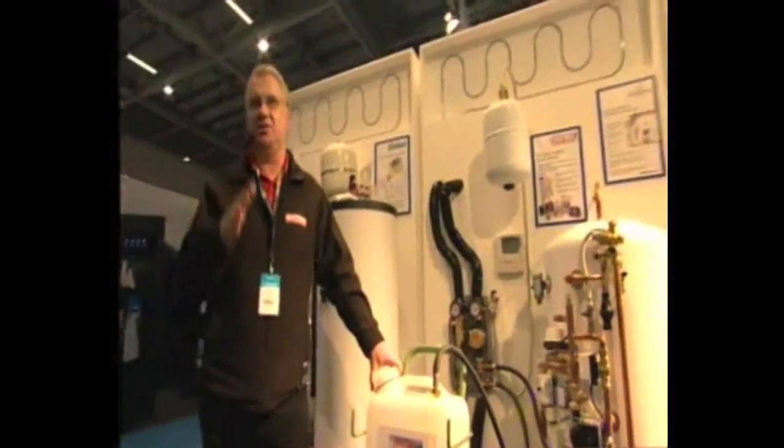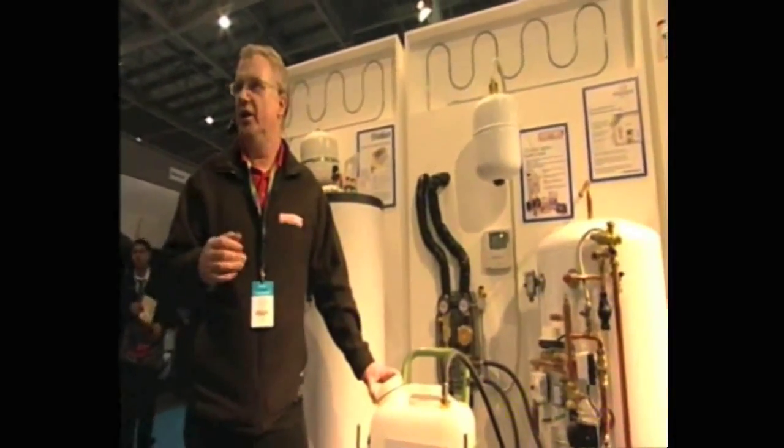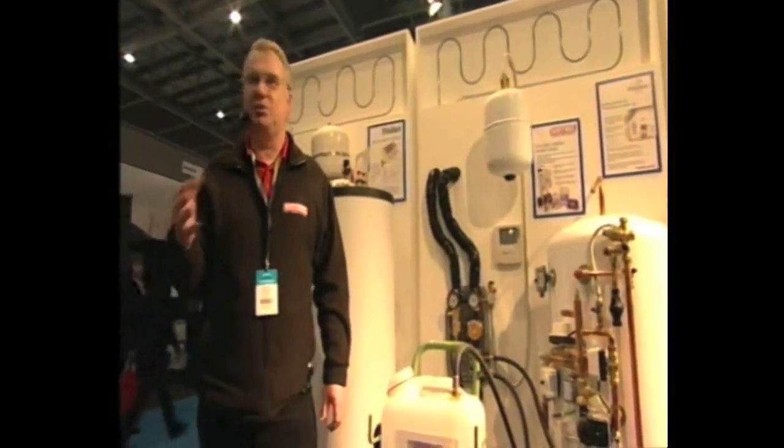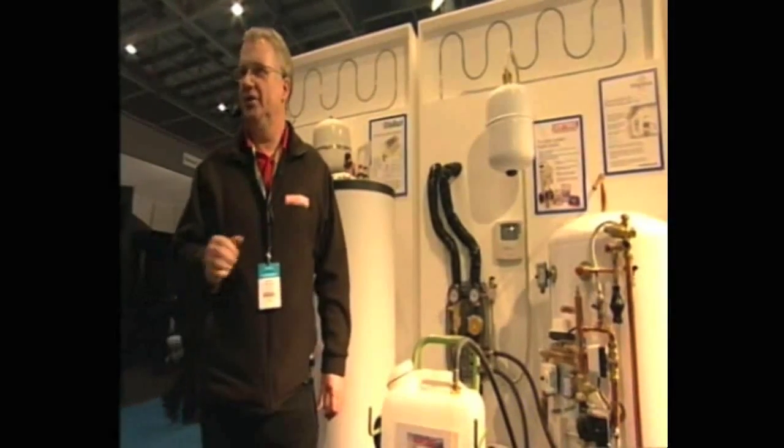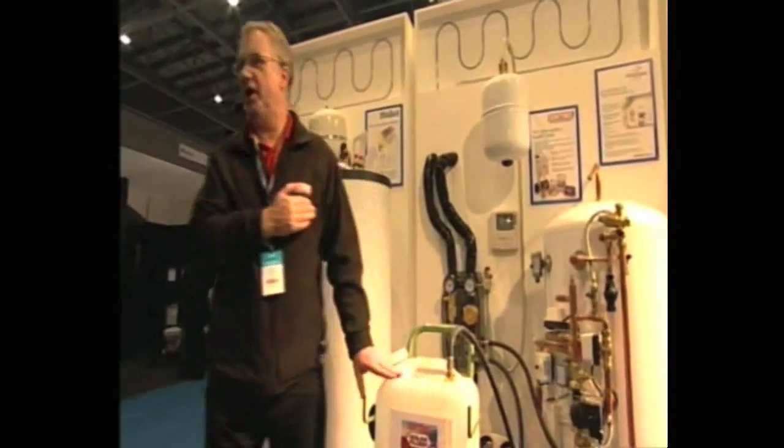And it goes more acidic. So as it becomes more acidic, then the glycol's breaking down and losing the frost protection. And also, some brands of glycol smell. Because it breaks down to a lactic acid and you can smell like a milk-like smell. So it's quite important at that stage, you need to pump back, connect it back to the system.